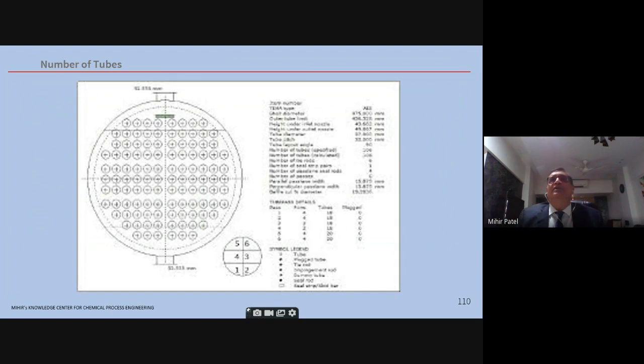So number of tubes depends on fluid flow rates, available pressure drop. So number of tubes is selected so that the tube side velocity is between 0.9 and 2.4. Okay. Lower velocity to limit fouling, while upper velocity to limit erosion. And the shell side velocity of about 0.6 to 1.5 is maintained. So normally number of tube passes are 1 to 10. You don't want too many above that because pass partition leakage will occur through the stream basically. Heat transfer will be reduced. Always remember, in shell and tube exchangers and air-cooled exchangers, the turbulence is very important because that contributes to better heat transfer.